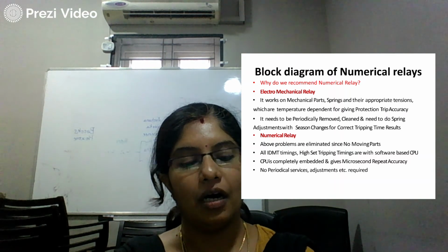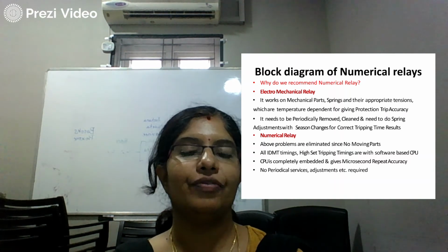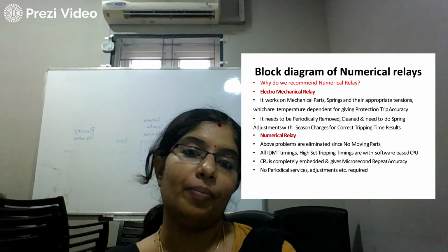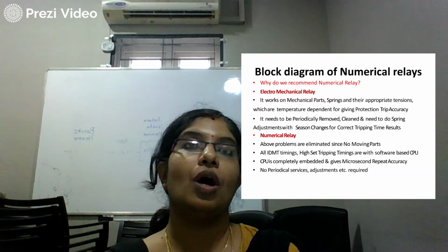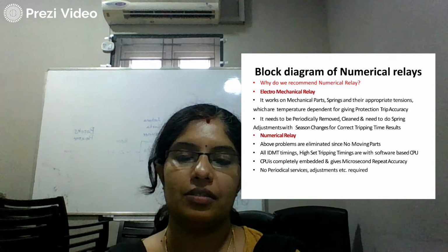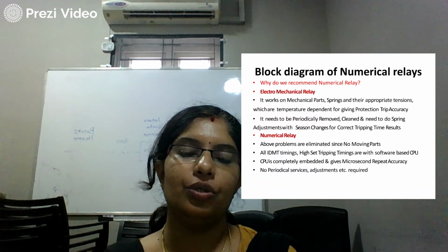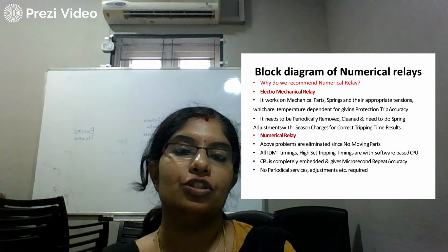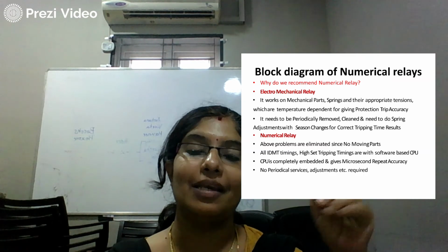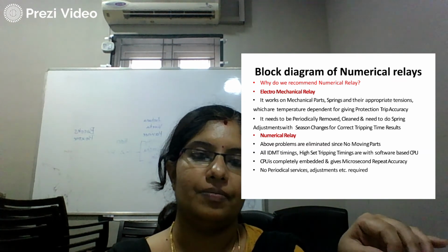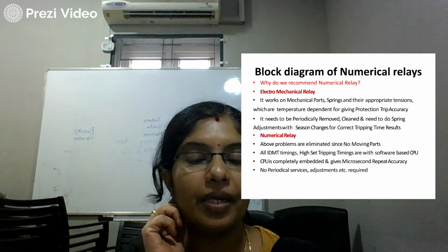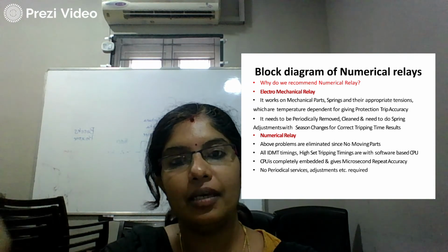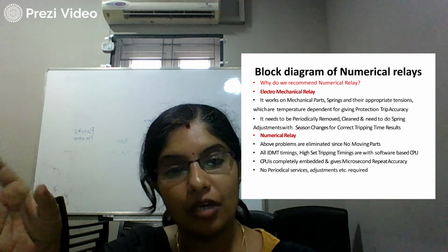So, for example, let us take that you have a 10 ampere current. And if the machine is operating beyond 10 amperes, maybe at around 18 or 20 amperes, at that time what should you do? Immediately the relay has to trip off. The relay has to give a signal to the circuit breaker so that the disconnection takes place within fractions of a second. The healthy part of the circuit should be isolated from the faulty part.